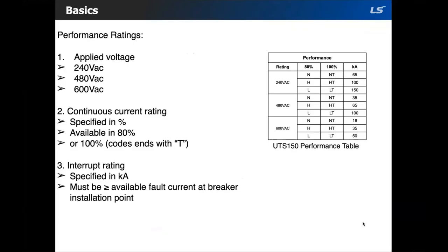Second, specify the continuous current rating requirements for the MCCB. The continuous current rating of an MCCB is the amount of current it's designed to continuously carry in open air. Each breaker is designed and calibrated to a specific amperage or current rating. So NFPA 70, the National Electrical Code, allows breakers to be applied to a maximum of 80% of the breaker's continuous current rating. Keep in mind that intermittent currents up to 100% of the breaker's rating are permitted, but continuous current applied is capped at 80%.